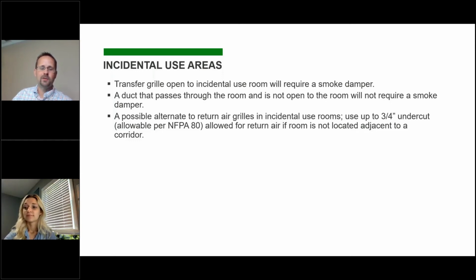And so it would be a 1 hour fire barrier. However those exceptions work, you may or may not need a fire damper when you penetrate those. And again, it's a smoke resist, or it restricts the passage of smoke. It's a smoke partition. So if you have a transfer air, you may need a smoke damper.